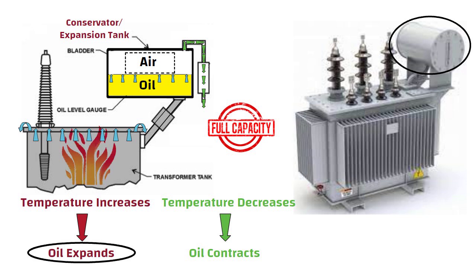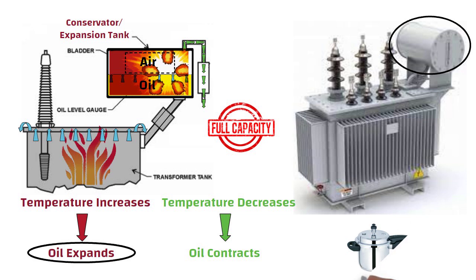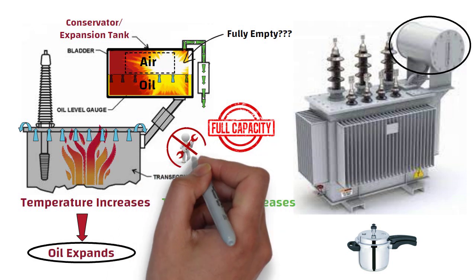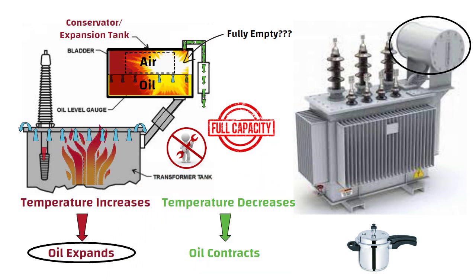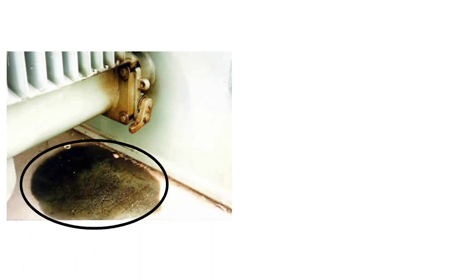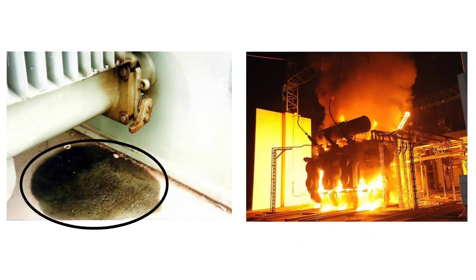If this air won't go outside the conservator tank, then the conservator tank can blast due to pressure. Same mechanism happens in a pressure cooker. Now the question is, then why can't we keep this expansion tank fully empty? The reason is, suppose the transformer is not maintained properly, then the oil level in the transformer drops. Then the oil present in the expansion tank will come here and maintain the proper level of oil. If all the oil leaks from the transformer, then the transformer may catch fire.